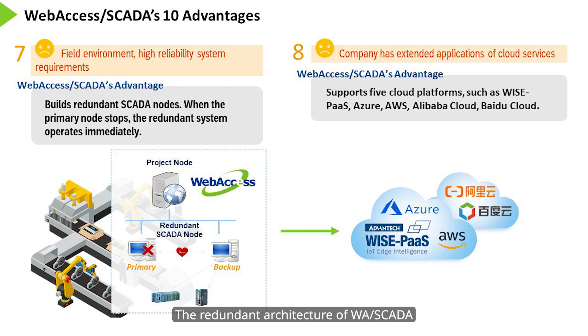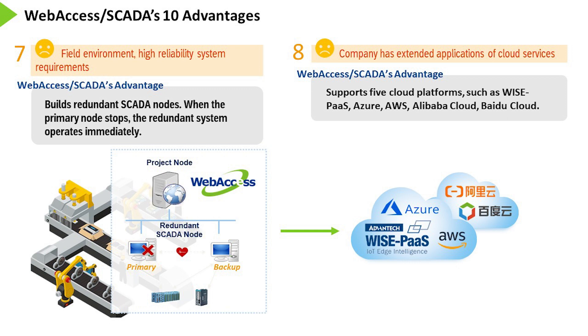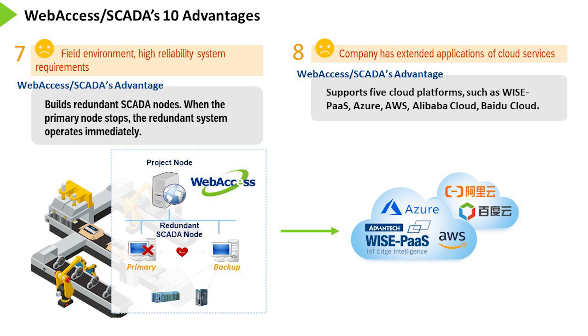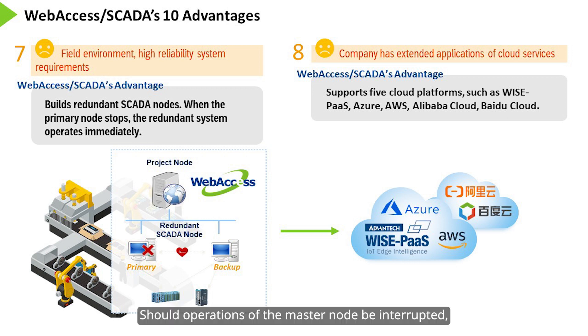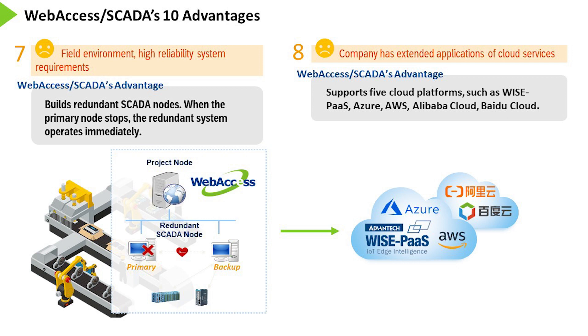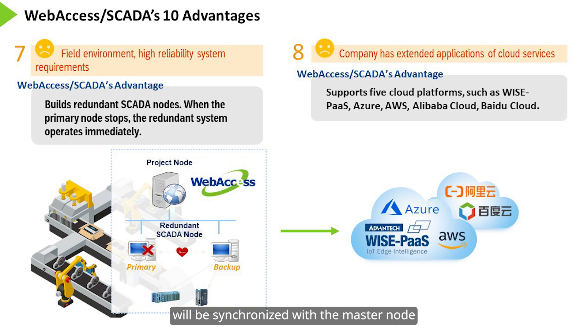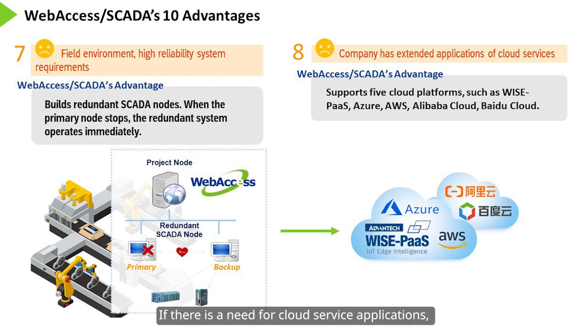The seventh advantage addresses sites that demand highly reliable operation and cannot afford equipment downtime. The redundant architecture of Web Access SCADA can be adapted to build redundancy into the SCADA nodes. Should operations of the master node be interrupted, the redundant backup nodes will go online immediately to continue working. When the master node resumes operation, the data that was collected by the redundant nodes will be synchronized with the master node and no data will be lost.